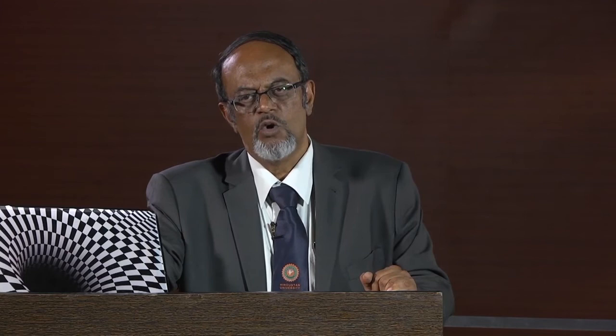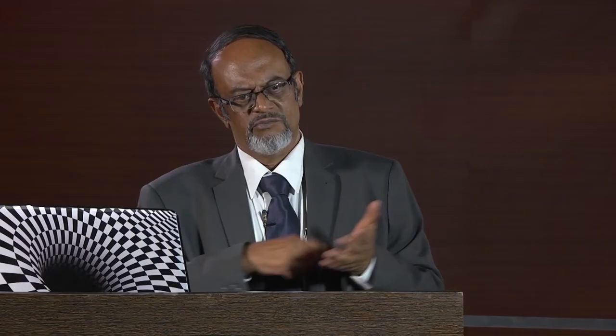Because of all these limitations, the more generally used system is the spring control. Here the restoring force is provided by a non-magnetic spiral spring, typically made of phosphor bronze. This spring is mounted on the shaft of the pointer — a spiral spring is like the spring in your watch or clock. When the pointer deflects, the spring gets twisted in the opposite direction, so the spring tries to restore the pointer. The twist on the spring, because of the pointer movement, creates the restoring torque, which is proportional to the angle of twist.